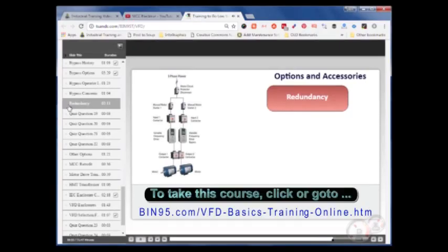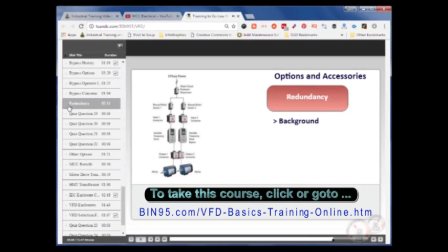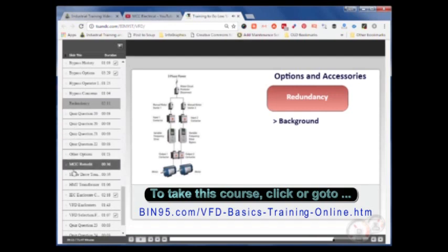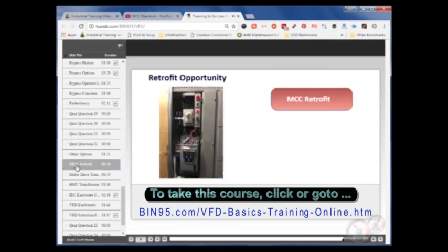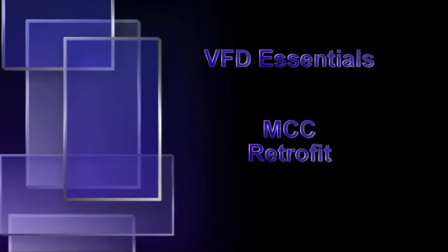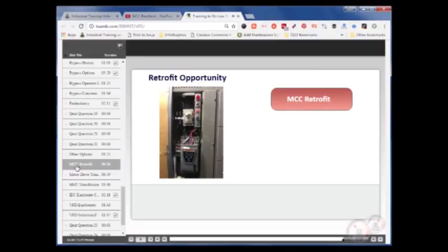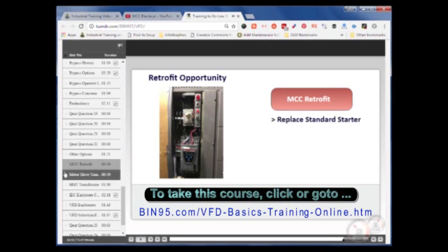Redundant VFDs are a logical choice for critical applications. As seen here, they work on the principle that if one VFD fails, full control and protection are maintained by a second VFD that automatically takes over. Redundant VFDs have been around for years, but only recently has this concept become cost effective as VFDs, because of their compact size, can be retrofitted into existing motor control centers.